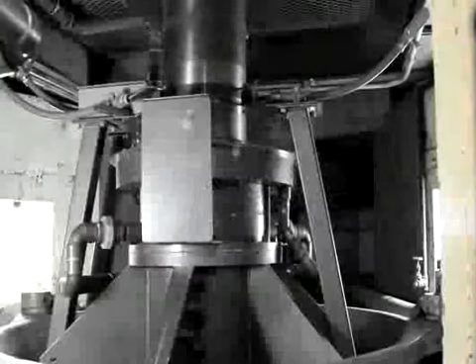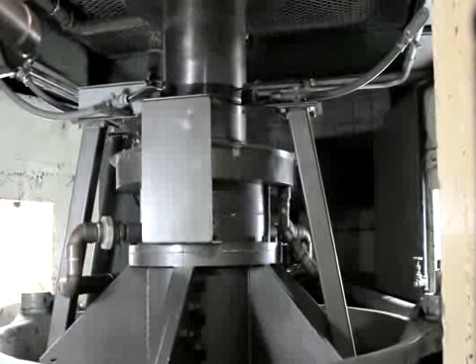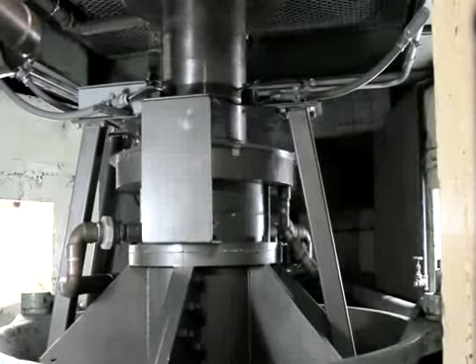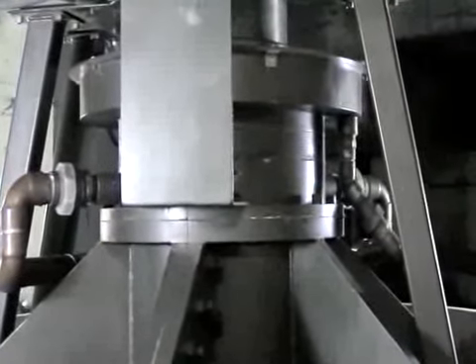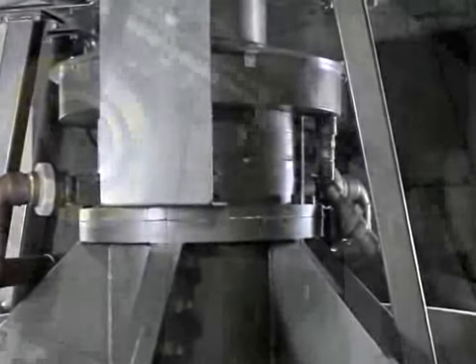In this view of a larger, previously converted turbine, you can see the seal water basin on the top, catching the water leaking past the seal and delivering it downward through the copper pipe on the left, and into the integral discharge duct leading to the low-pressure area above the runner. In other turbines, the bearing discharge may have to be piped away rather than this convenient method of disposal.